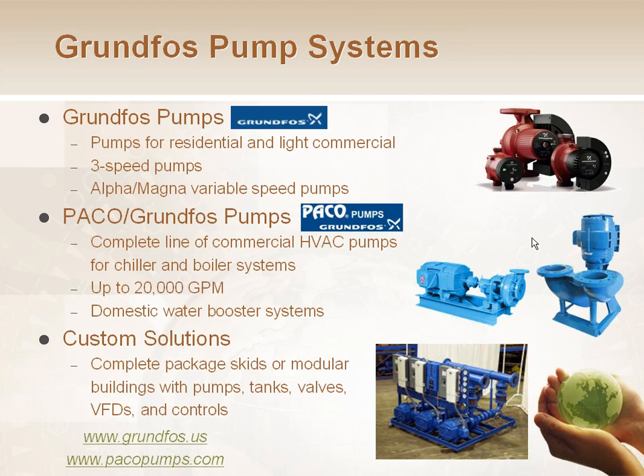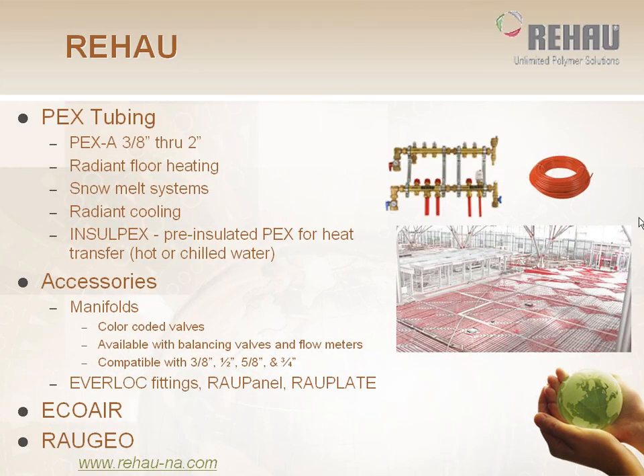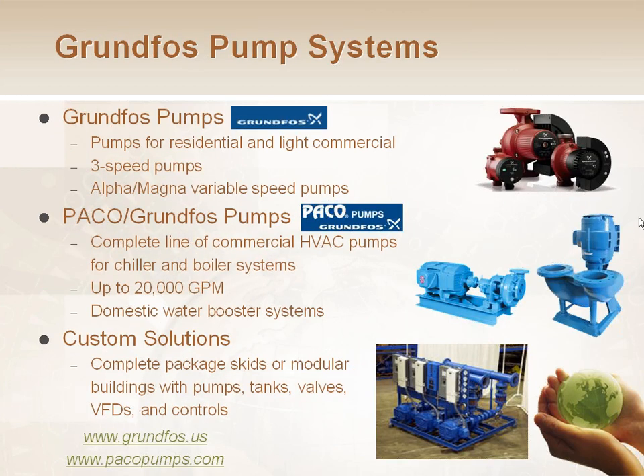Pumping systems, we have several different lines of pumps here. This is showing you the Grundfos and Paco pumps. We also have Bell & Gossett pumps that we use as well. But we use Grundfos a lot on boiler systems residentially and commercial. For the larger commercial stuff, we typically use Paco, P-A-C-O, and that is a company owned by Grundfos. They bought them a couple years ago, and that's where we get all of our bigger pumps from. They go up to 20,000 GPM, so quite large.